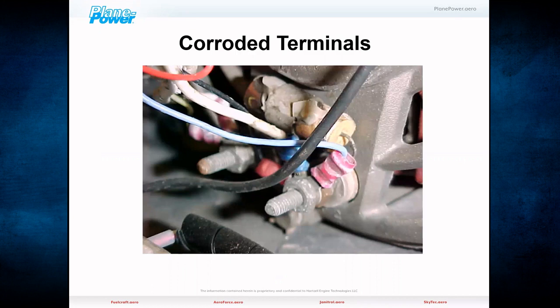Corroded terminals, I guess so. It's just one of those things—if you're having a problem, bust them loose, tighten them back up, just to make sure. That piece in the middle, that little capacitor between F1 and F2, notice that it's on there. We don't recommend you put that back on. However, some of you reminded me that part is in the electrical maintenance manual for the airplane and is an available part, so it would need to be reinstalled.